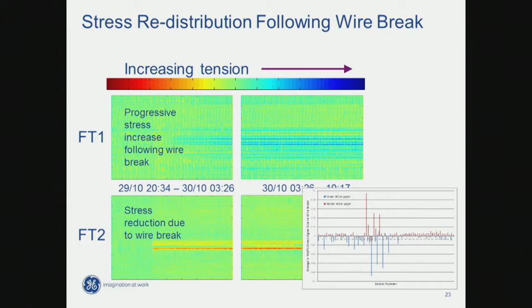But interestingly, in this particular load combination, and this effect will be dependent on the load combination, what you have is pickup of that load in the other layer. So much of the load change, the reduction, is picked up by the other layer. What this graph shows is over a period of time, a snapshot: if you subtract the response of the signal between that time and this time, this is the delta. The red is the load loss in the outer wire layers, and the blue is the load pickup. You have to trust me that over a period, you actually do get equilibrium - the load lost is the same as the load picked up.